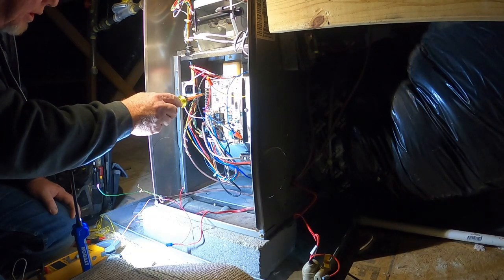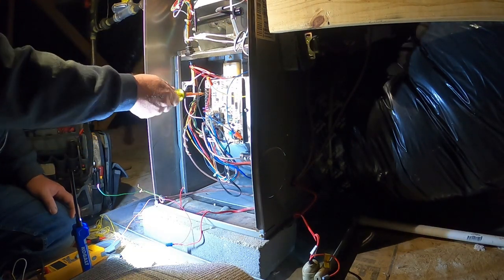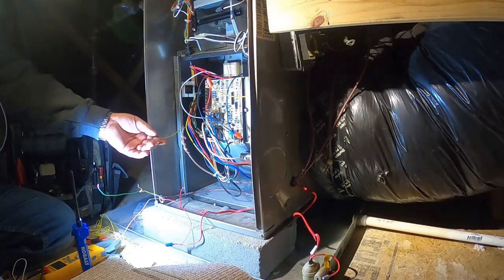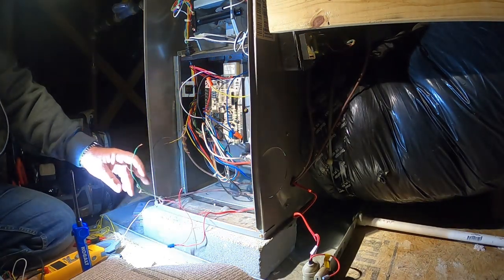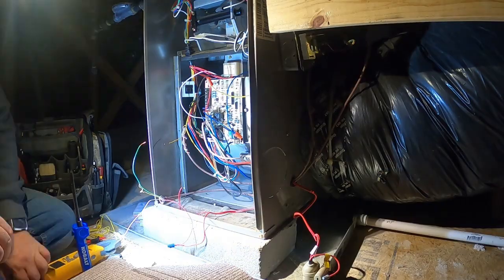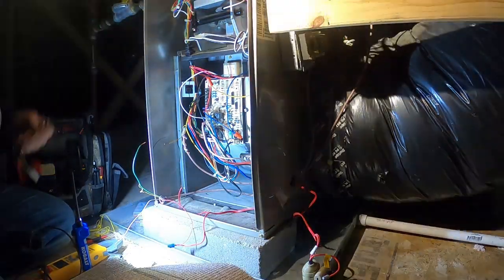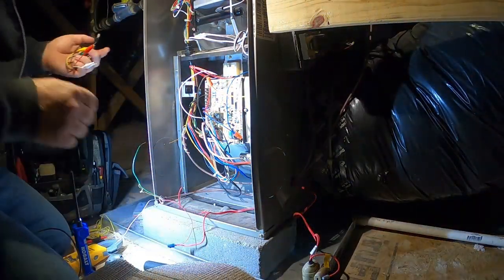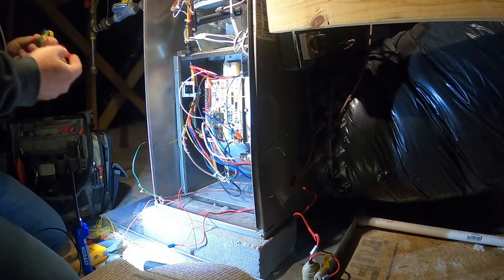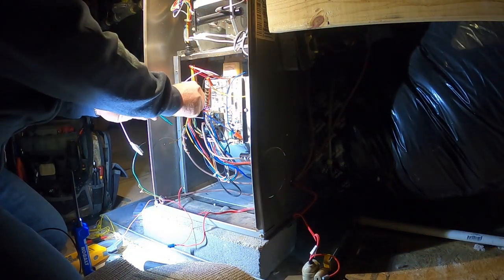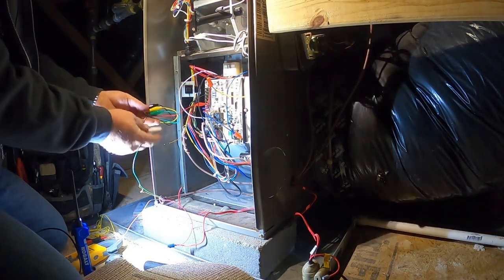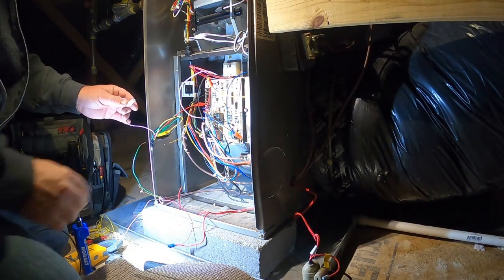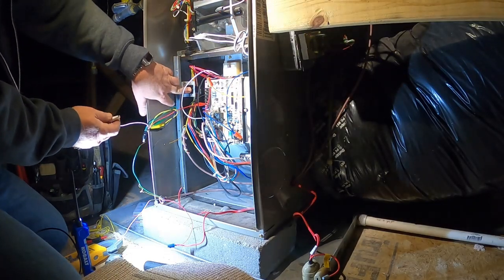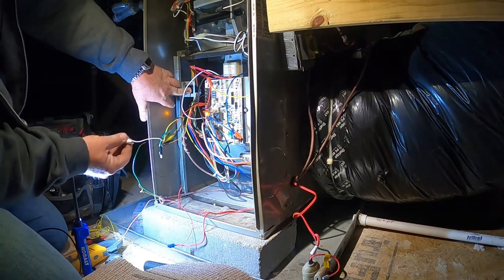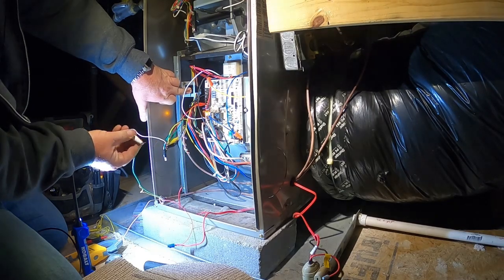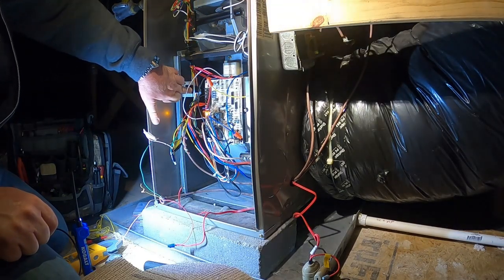So I'm gonna hook common up to the board. And then we're going to jump 24 volts to our outdoor unit and our blower and see what happens. And keep our fingers crossed, I guess. This is all it was, and she didn't need a new furnace. So anyway, all right, power back to the board, jump out the blower. See what happens.